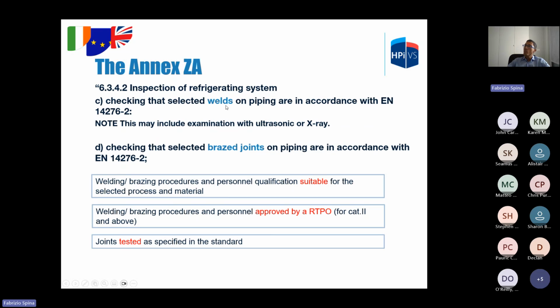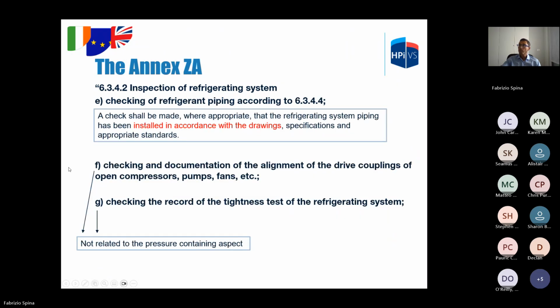Checking that selected welds on piping are in accordance with EN 14276. Same thing for the brazing joints. And basically it means that welding and brazing procedures and personnel qualification are suitable for the selected process and material. Procedure and personnel must be approved by a recognized third-party organization for category 2 and above piping, and joints must be tested as specified before in the standard.